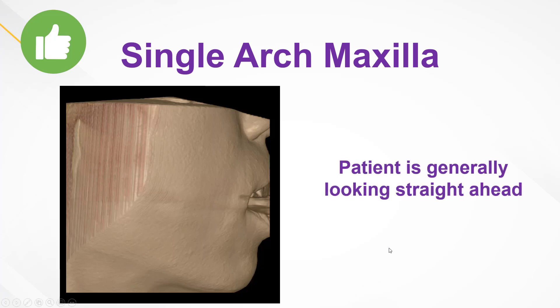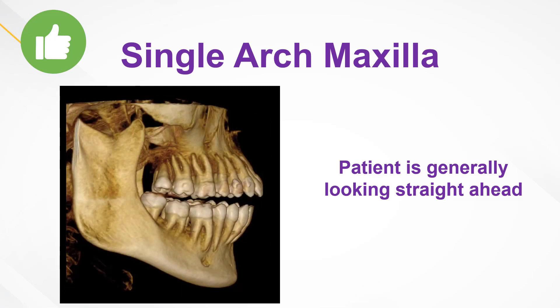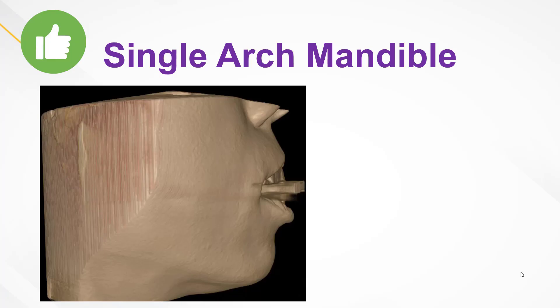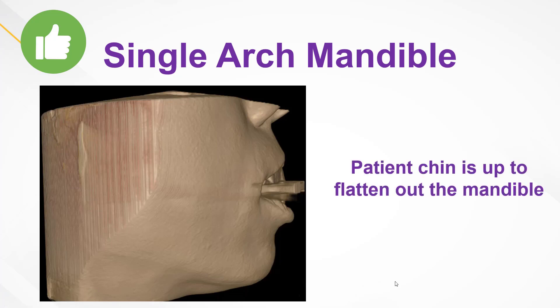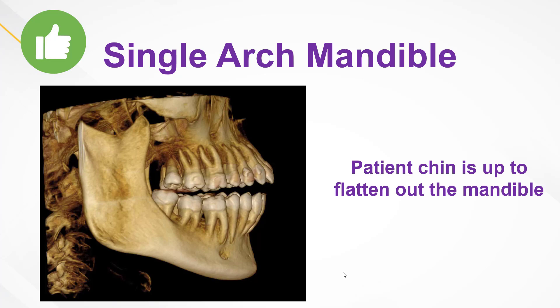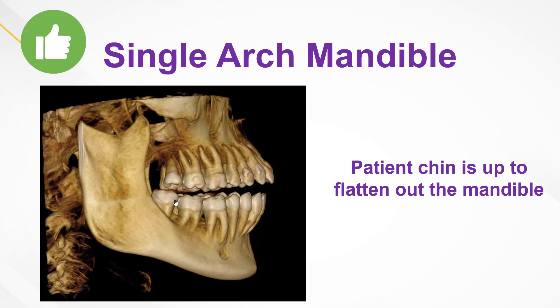If you're capturing a single arch — just the maxillary arch — the same instructions apply: the patient looks straight ahead and the maxillary arch is nice and parallel to the floor, making it more easily visualized in the 3D software for planning and diagnosis. When it comes to capturing just the mandibular arch, you'll notice the chin actually needs to be higher up. Raising the chin flattens out the mandible so it's more easily visualized in the software, just like the maxillary arch. Having the chin up translates to a flattened, well-oriented mandible in the CBCT software.